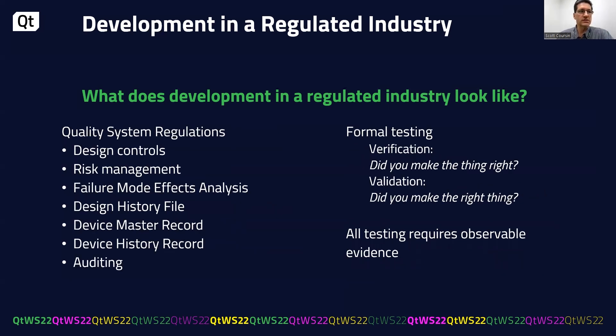The quality system regulations lead us to use the following tools and techniques. Design controls give structure to the design documents, all the way from requirements to implementation. Risk management and FMEA are used to ensure safety. The DHF documents all aspects of the design and is kept for the entire life cycle of the product, which can be many years. The DMR includes all instructions and drawings used to manufacture the device, and the DHR is a per-unit record of the device's adherence to the specifications. Auditing is used by regulating agencies to make sure that companies are in compliance.